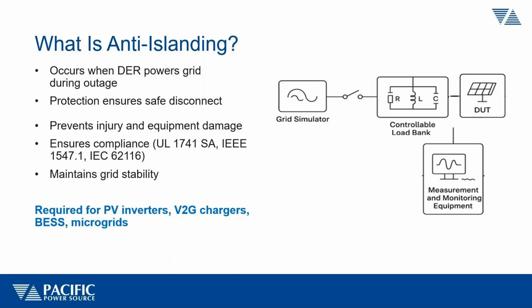So the test setup for that is simplified on the right-hand side. You see the grid simulator that will simulate the grid for test purposes. Then the unit under test, any PV inverter or any regenerative inverter. And then in between, you need an RLC load bank or load that simulates the grid impedance. Because that's usually what happens when the grid power goes out and there are other energy sources connected to it: they will see an impedance and they will feed that impedance. So it will actually continue to push into that. And that's what is being simulated here, to see what a grid condition would look like when that happens. So in order to do that, you have to simulate those conditions using an RLC load bank.